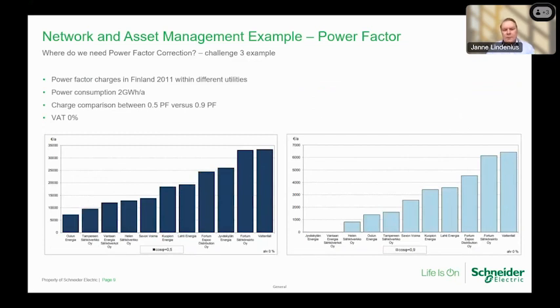What we have here is a screenshot from a study done for a utility provider in 2011, located in the second biggest city in Finland. The simulation of the effect of the power factor is made for a utility customer using 2 gigawatt-hours of electricity per year. Simulation data points are taken from real-life recordings averaged over 2009 and 2010 from the utility data. We can see from the chart on the left side that reactive power compensation charges can be 5 times more expensive depending on the utility area you are located in. More interestingly, if the customer would improve the power factor to the 0.9 level, the highest charge would drop from the 32,000 euro level to the 6,500 euro level. That results in a whopping 26,000 euro savings per year. Next slide, please.